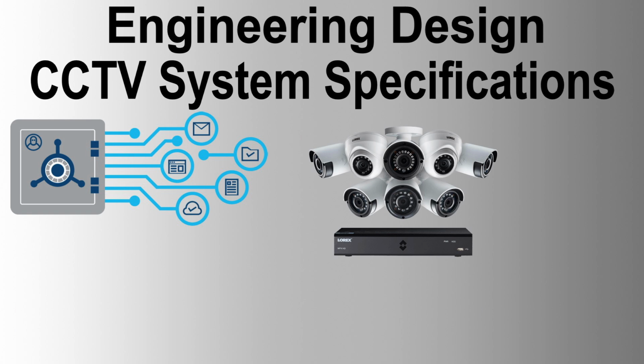Platform: the CCTV operator stations shall operate on an IP-based Ethernet network platform, incorporating various modules required for effective management, including surveillance operations, recording, replay, and archival of video image records. Capability to perform video image search shall also be incorporated. Storage: operating stations shall provide enough memory space for 2 weeks of online video storage and access to high-capacity archiving mechanisms for the removal of stored video to offline media.